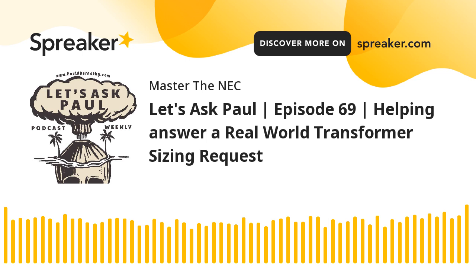Now, you say that this HVAC unit has a load of 78 amps, and you say the label tells us the maximum overcurrent is 100. Okay, and we're going to try to keep this simple. So when I'm sizing this transformer, that's the next step, I have to make sure that at the load, which is on the secondary side, this transformer can handle 78 amps.